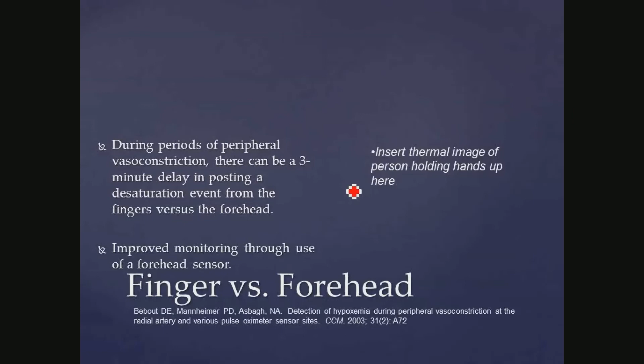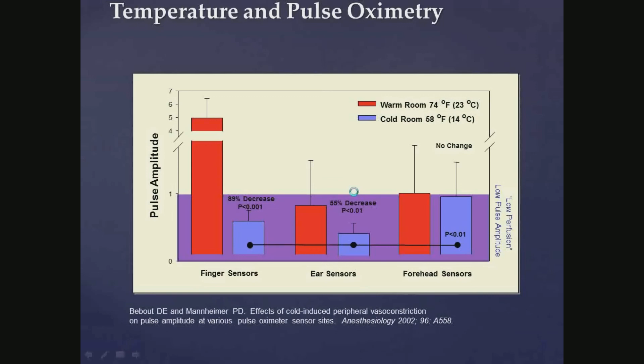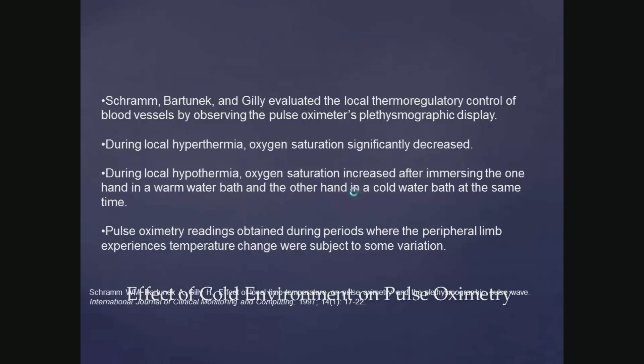Red is the warm room. You can see it's a little bit higher than the cold room. Again, in the cold, vasoconstriction is going to have a problem getting a good signal. This is looking at pulse amplitude. And again, this is talking about hypothermia and the regulatory control of blood vessels. Peripherally, when you're cold, you tend to shut down, and that's why you end up losing a lot of the signal. And that's the argument for going to that kind of a process.